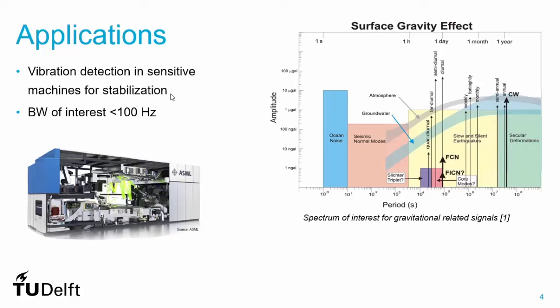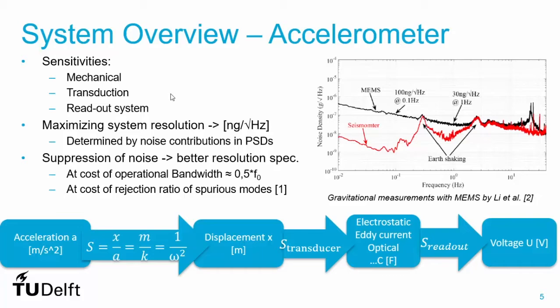In terms of the system overview, we go from the measurement — the acceleration — to the displacement domain. We have a mechanical sensitivity defined mainly by omega squared, which is the resonant frequency. In a relative open-loop mass-spring system based accelerometer, this is determined by the ratio of mass over stiffness. Then we have the transducer to the electrical domain, which can be electrostatic, eddy-current based, or optical.